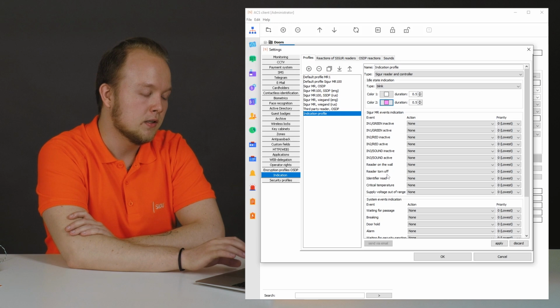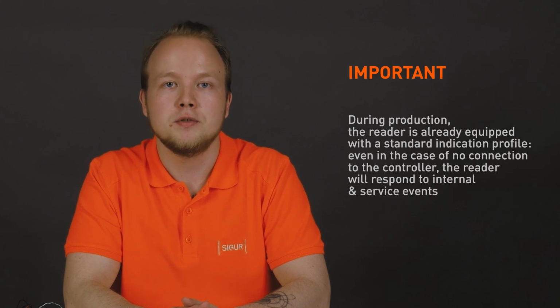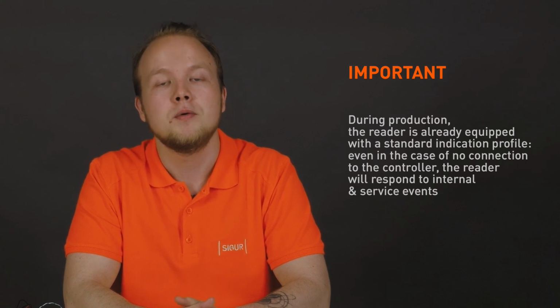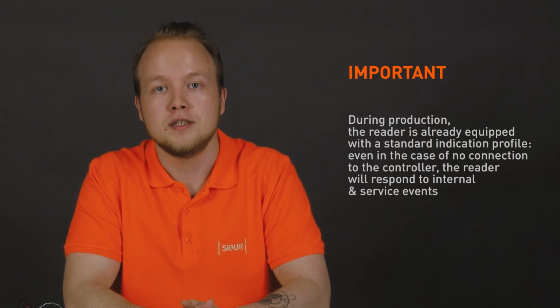If the temperature of the reader exceeds the normal limits, a reaction set for the event of temperature out of range is triggered. If the power supply voltage of the reader exceeds normal limits, a response is triggered. It is important to note that reactions to internal service events of the reader can be triggered regardless of the interface through which the reader is connected to the controller.